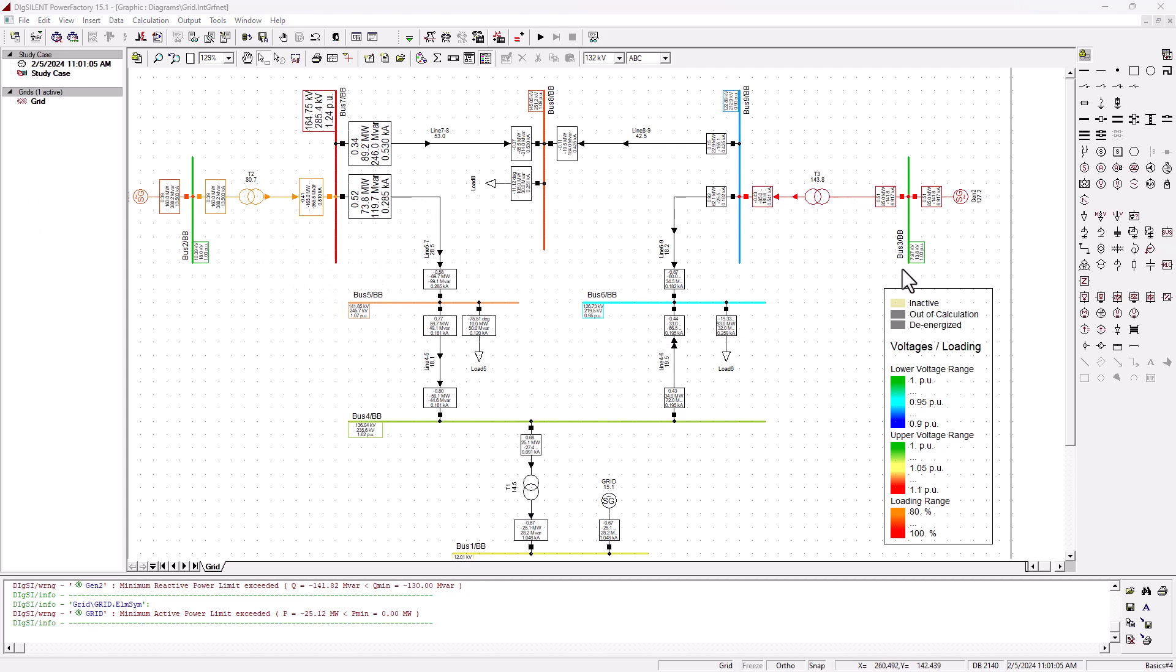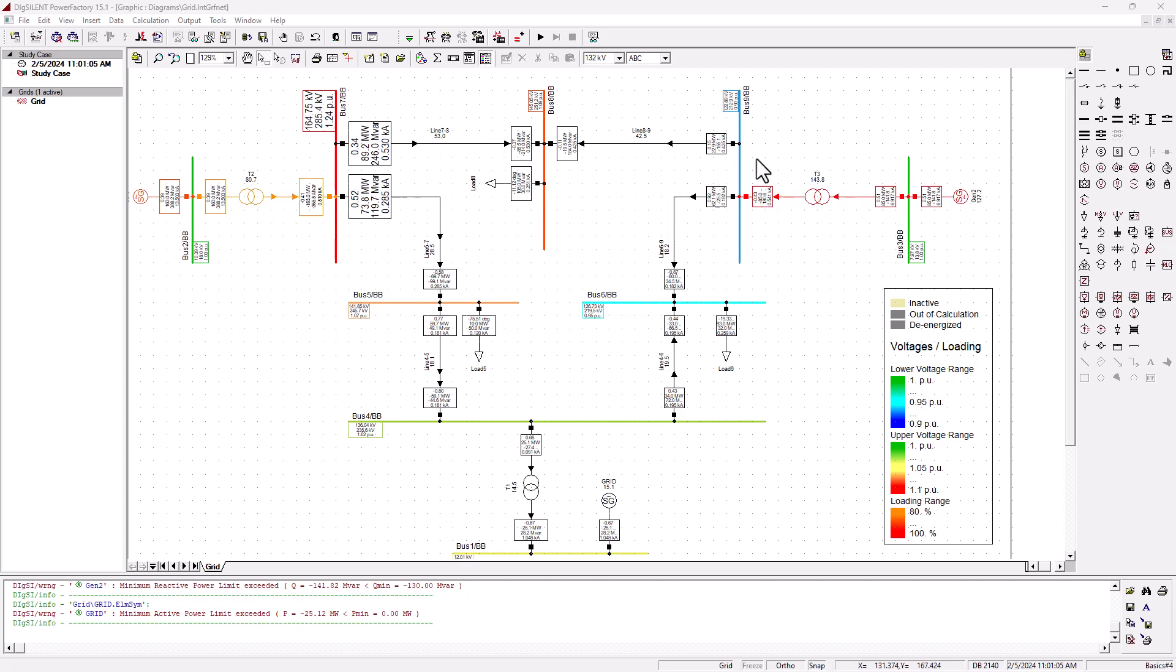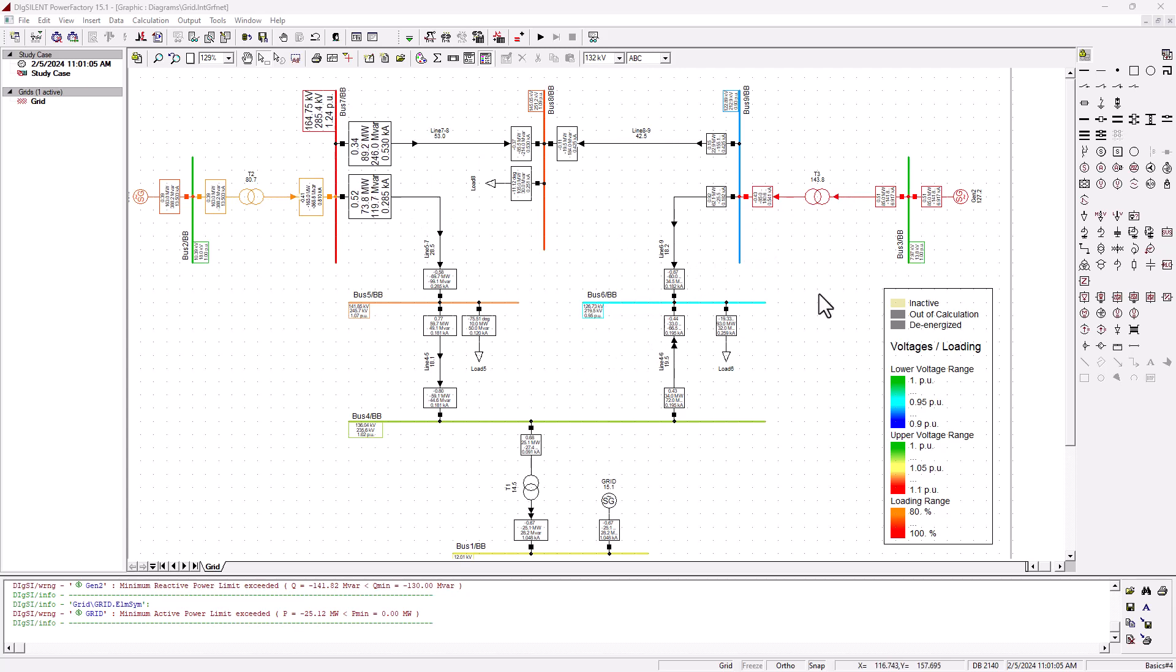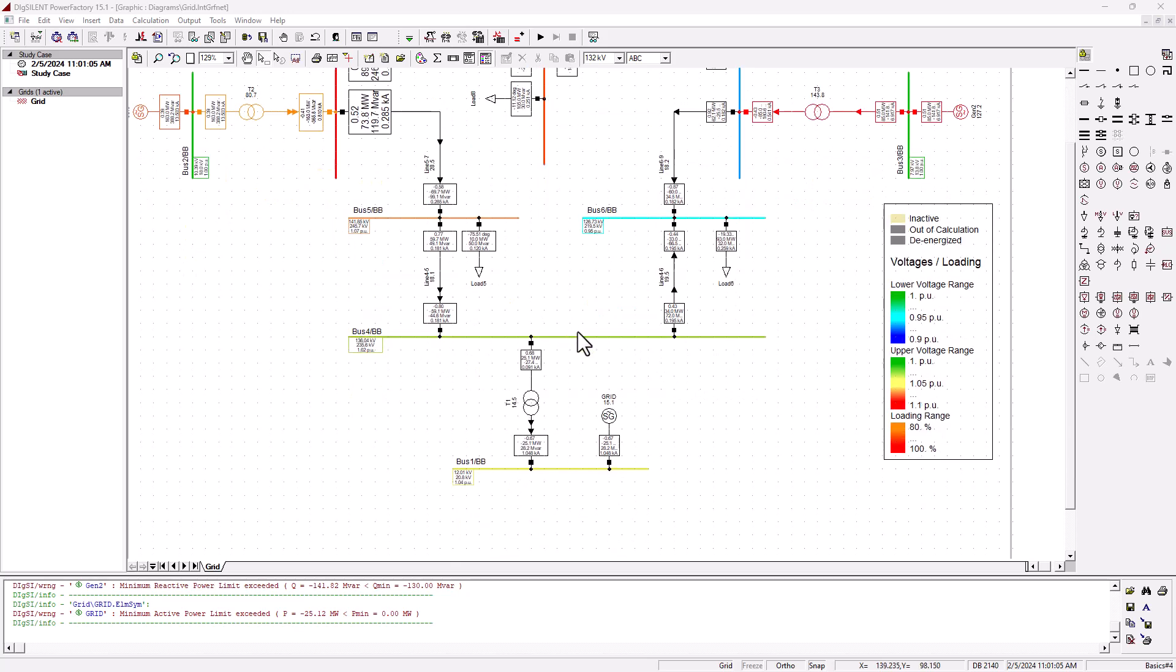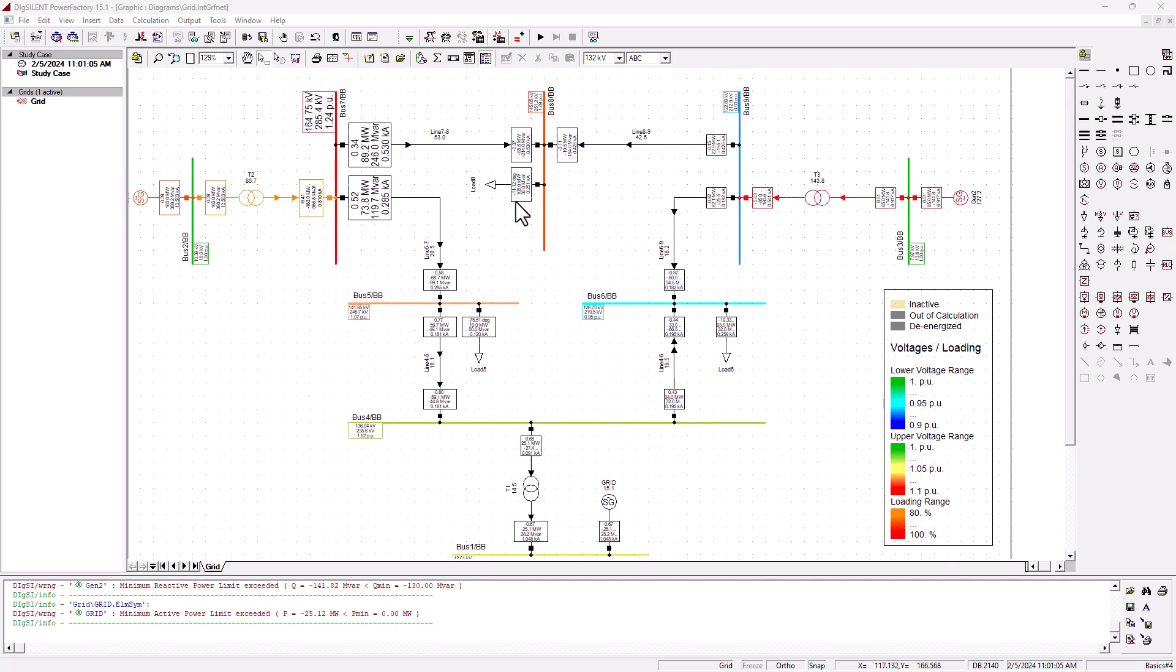In closing, please note that reactive power, they are very important. Generators generate reactive powers for voltage regulation on your network and for power factor corrections. You've got all sorts of things that distort the power factor and cause instability. Generator will have to generate reactive power to compensate that so that there will be grid stability and to compensate on all the line losses.